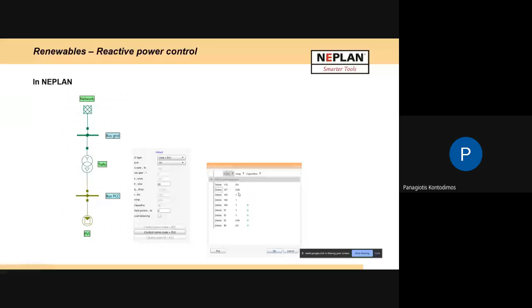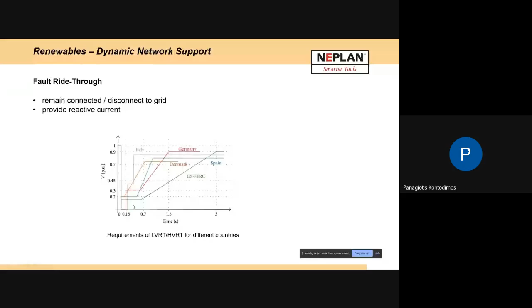Apart from that, we can have fault ride-through here; for example, different countries in Europe, Italy, Germany, Denmark, give rules on how the voltage should recover in case we have a fault. Very often we want to simulate this also in our simulation. What we are doing is giving this information to the connection with the grid. Here is my installation, and here is my grid connection, and I provide the fault ride-through, which is the rule on what I should try to comply with in case there is a fault.